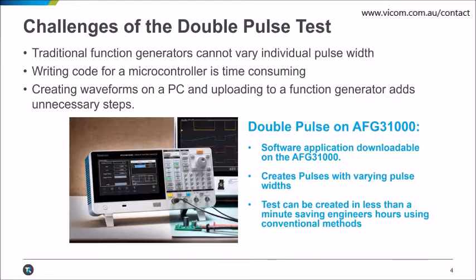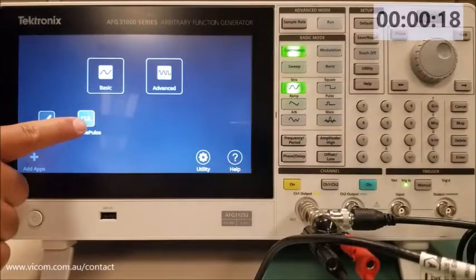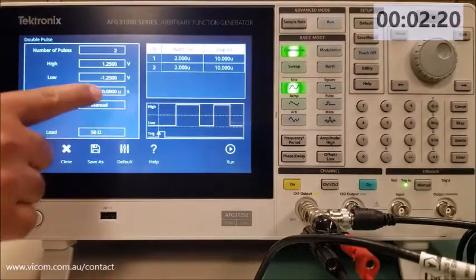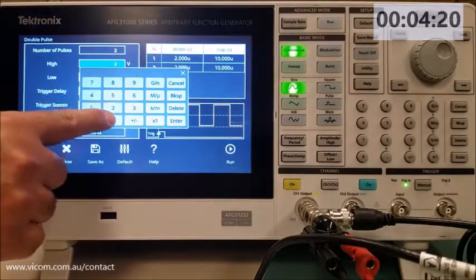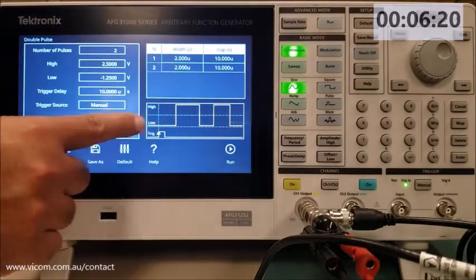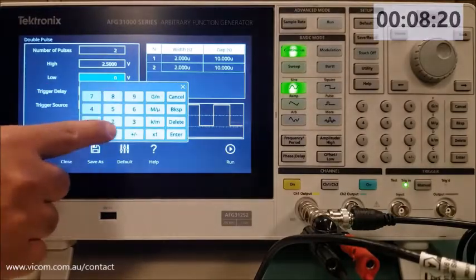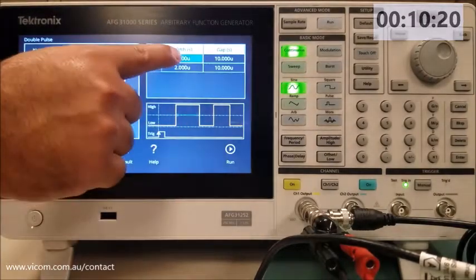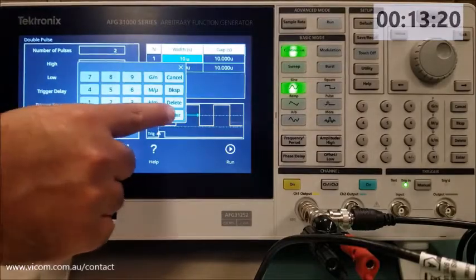The software is downloadable and users can create their custom pulses in less than a minute. The app can be found on the home screen and offers a variety of pulse configuration options, including the number of pulses, high and low voltage magnitude, trigger delay, trigger source, and the pulse width settings.